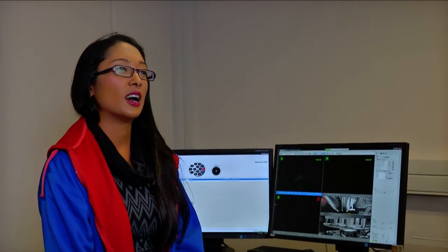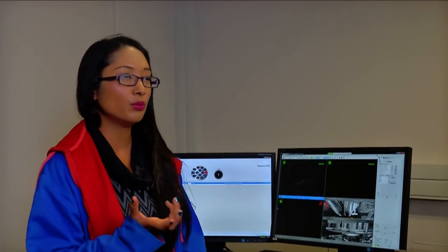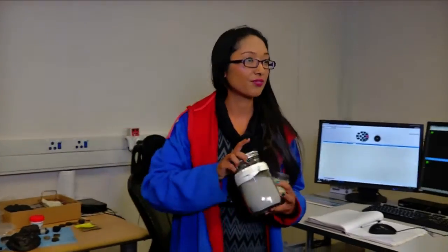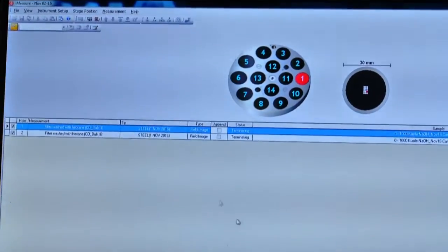So how we prepare the samples: we usually get them as a PF sample, which is pulverized fuel, and once this is combusted you get fly ash. We prepare blocks by taking a bit of that powder and mixing it in wax, then polish it down to a really fine 3-micron finish, and load it into the instrument to be analyzed. I'll open up the instrument.